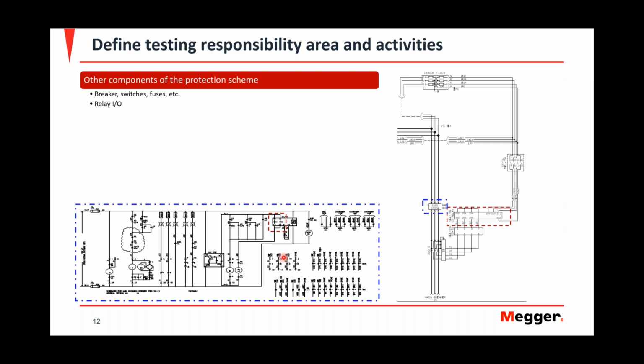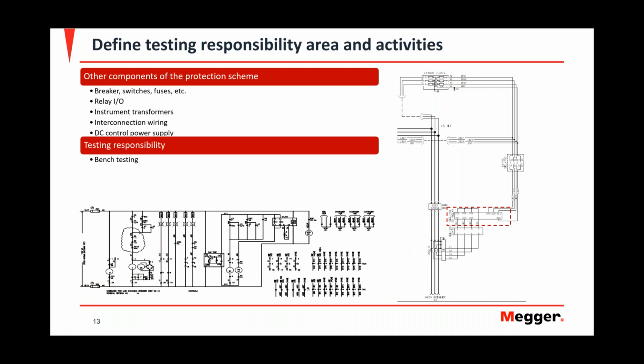You've got to know the other things that are in the system: your instrument transformers, your PTs and your CTs. Know the location, know what they do. Know all the interconnecting wiring between your input signals, in this case your PTs and CTs, and your relay. And the DC control, the power supply feeding DC power to the breaker control scheme. After you are aware of all the components that are part of this scheme, then you start to ask the questions: okay, but what am I responsible for?